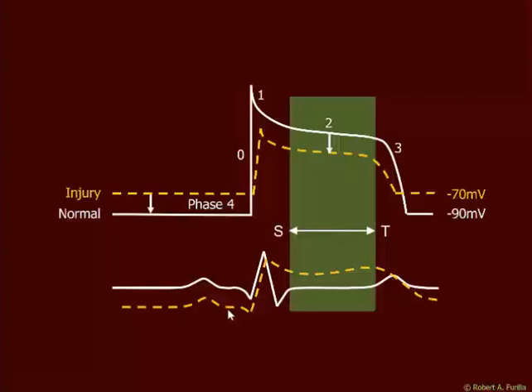EKG machines, however, are AC-coupled, which means they're going to determine the baseline — the diastolic period for the myocytes — and always correct it to zero. So we will never see a depression on an AC-coupled electrocardiogram. Rather, it will automatically adjust the baseline to zero, and all we'll then see is an ST elevation.